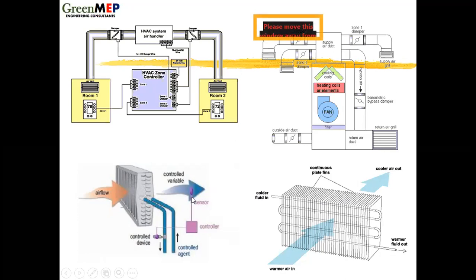There's a sensor to detect the discharged air temperature. The sensor feeds back to the controller. The controller knows the set temperature by the user. You set the temperature, for example, you use this to set the temperature. The controller knows the temperature you're looking for. It compares the set temperature with the actual temperature. And let's say the actual temperature is higher than the set temperature.